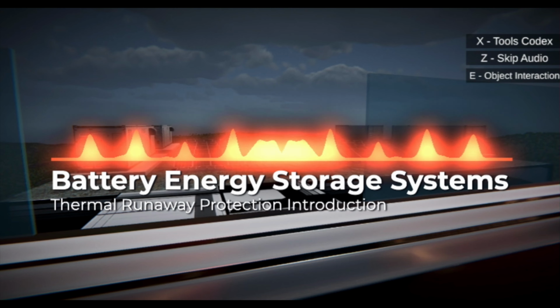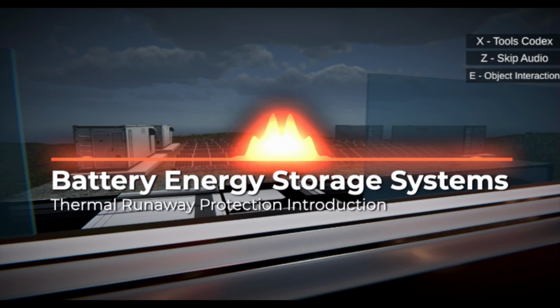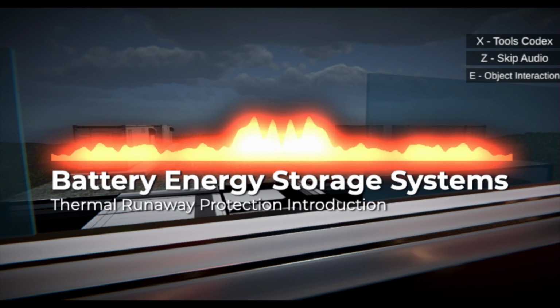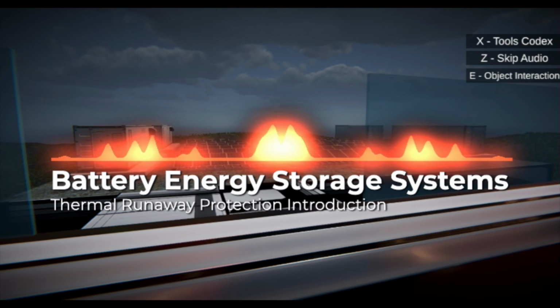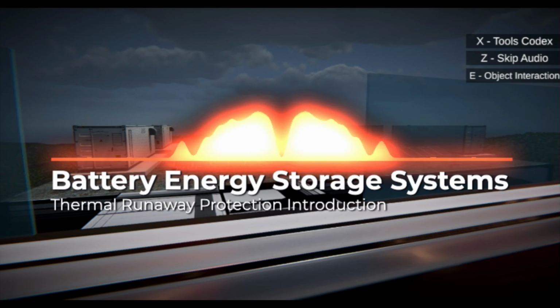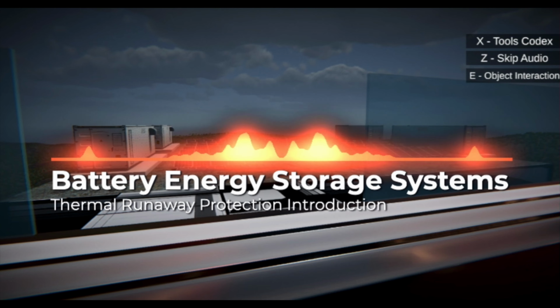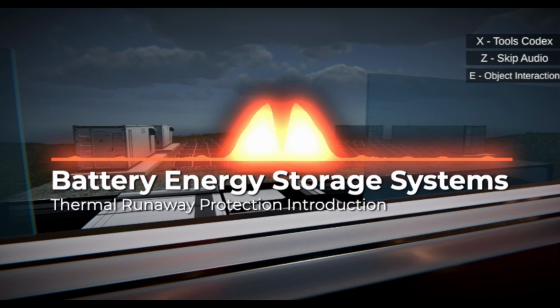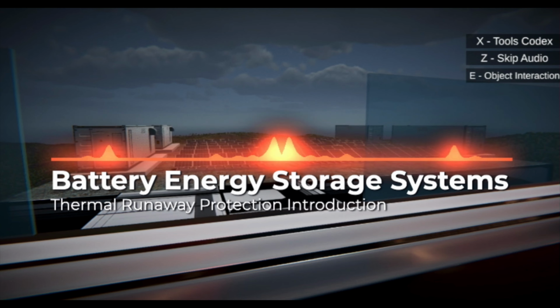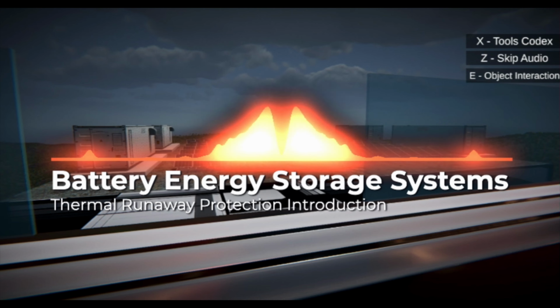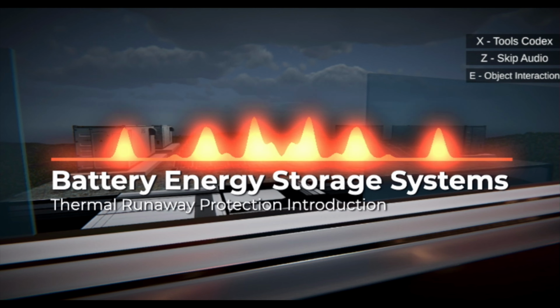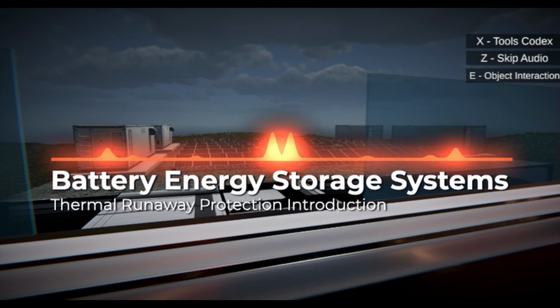To uphold the highest safety standards in BESS installations, Underwriters Laboratories, UL, has developed two pivotal standards, UL 9540 and UL 9540A. UL 9540 sets forth comprehensive requirements for energy storage systems, encompassing batteries, power conversion equipment, and associated components. This standard provides essential guidelines for manufacturers, system integrators, and regulatory bodies, ensuring that BESS installations adhere to rigorous safety criteria. In addition, UL 9540A specifically focuses on evaluating the fire performance of energy storage systems.